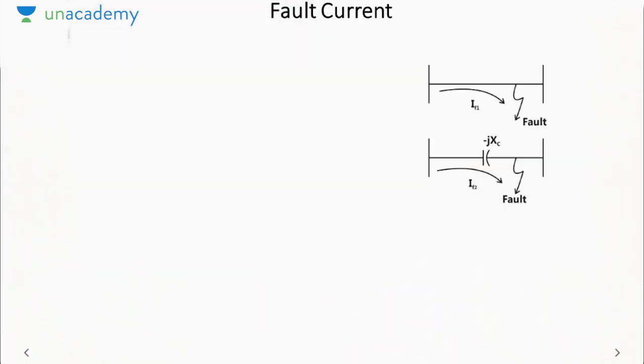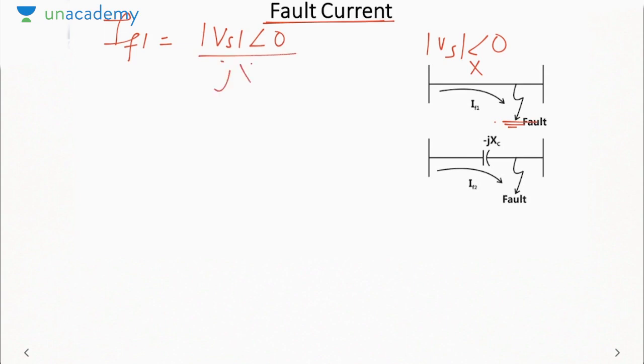Next, let us see the effect of series compensation on fault current. A fault usually means that we are grounding this line; we are considering a shunt fault. Here let us assume that the voltage is |Vs| angle 0. So what will be the fault current IF1 if the reactance is X? It is |Vs| angle 0 by jX, or |Vs| by X angle minus 90 degrees.